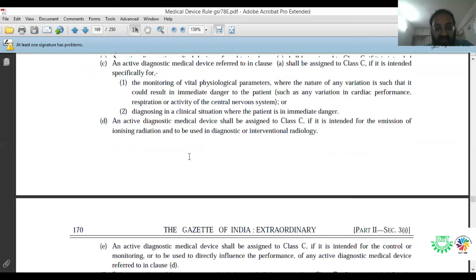So here you can say the active diagnostic medical device. We know that our device is going to be used for the diagnostic of very important vital physiological parameters. Here you can see subpart C of point number 13: active diagnostic medical devices referred to in clause (a) shall be assigned to Class C if it is intended for the monitoring of vital physiological parameters where the nature of any variation is such that it could result in immediate danger to the patient, such as any variation in cardiac performance, respiratory, or activity of central nervous system.